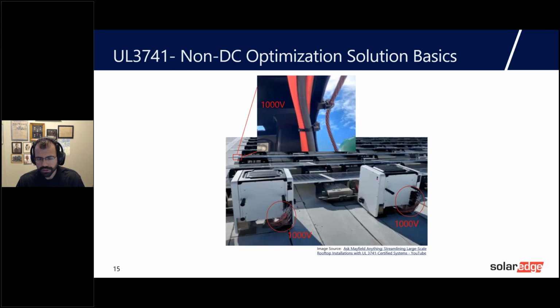To mitigate this risk, UL 3741 states that solar arrays need to be made safe and not allow any exposure to dangerous voltages during firefighting interaction. This means that every wire, module, or energized component in the array that can be accessed during firefighter operations must be protected from damage using robust wire protection measures, such as sturdy wire guards and conduits. It is at this point that some of these alternative solutions start to lose traction, and that's where we would like to open everyone's eyes. This is not due to any flaws in the 3741 standard itself, but rather to the way it is being interpreted by some manufacturers and certification agencies.